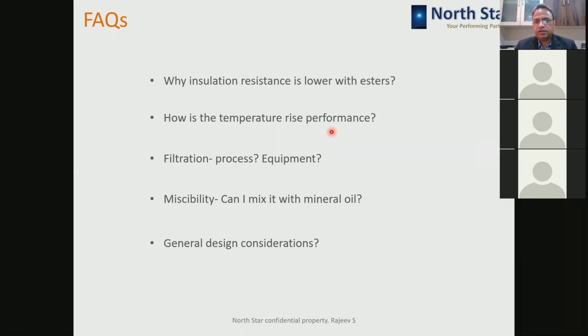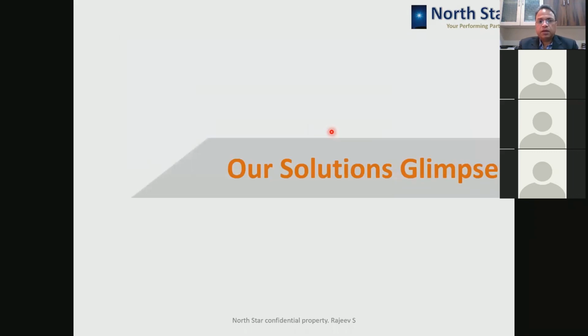Okay, general design consideration, as we discussed, up to 33 kV, nothing much major changes are required. You can increase your clearances and cooling duct size by around 5%, and that will be sufficient. But if you go for higher voltages, then detailed design considerations have to be given when you are designing the transformers. Okay. Now, with natural and synthetic ester, we are at the end of our topic.